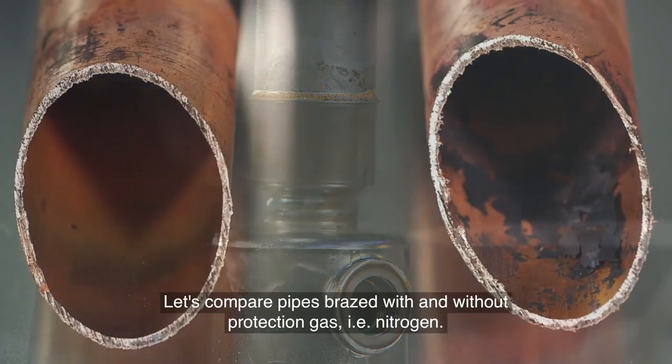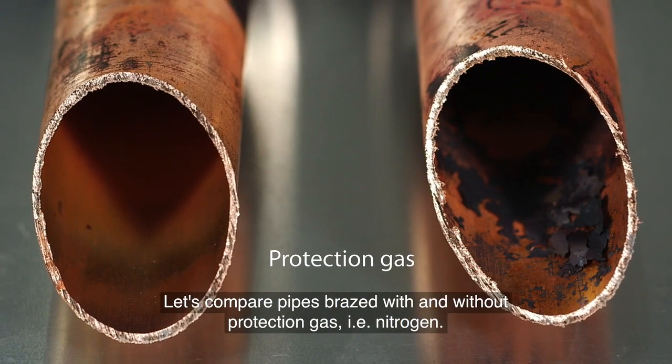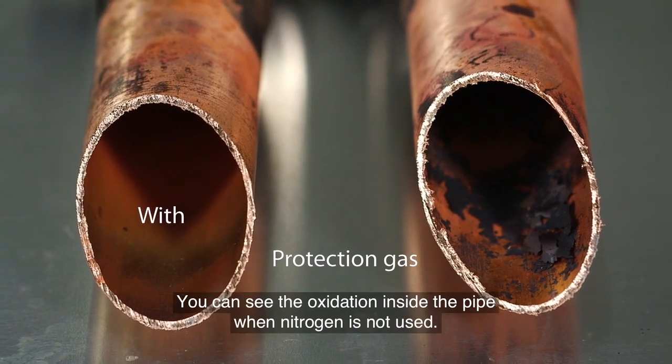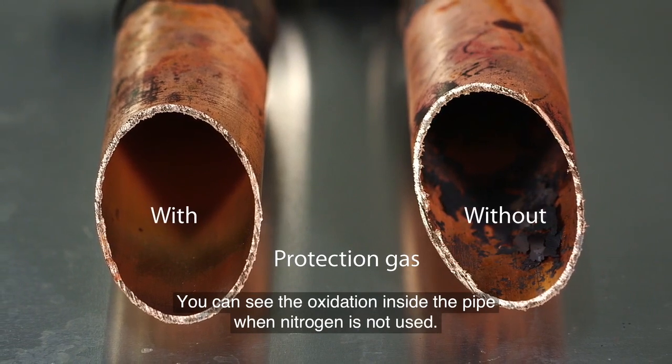Let's compare pipes brazed with and without protection gas, that is, nitrogen. You can see how clean the inside of the pipe is when nitrogen is used. You can see the oxidation inside the pipe when nitrogen is not used.